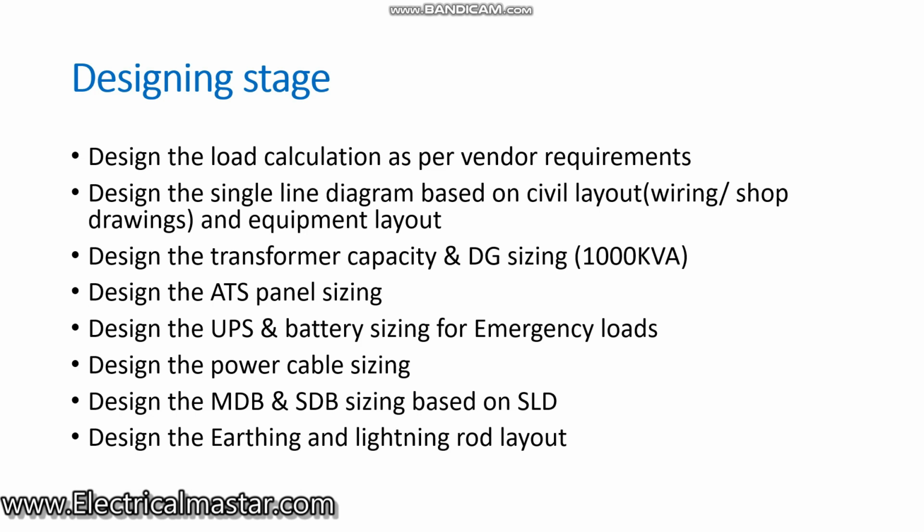And also, the final thing, you have to do the earthing. That is very important. For earthing, you have to make the earthing layout first, wherever you want to put the earth pit, and also you have to install the lightning rod, because it's 3 floors. As per the standard, for a minimum height of 20 meters, you have to use lightning rod installation. So I installed the lightning rod there, and connected it separately to the earthing in the ground for lightning protection. So these are the designing documents. Before you start the job, you have to prepare these documents.